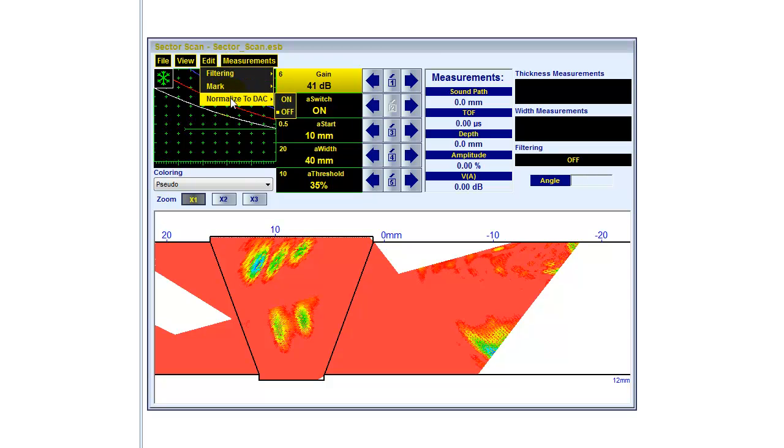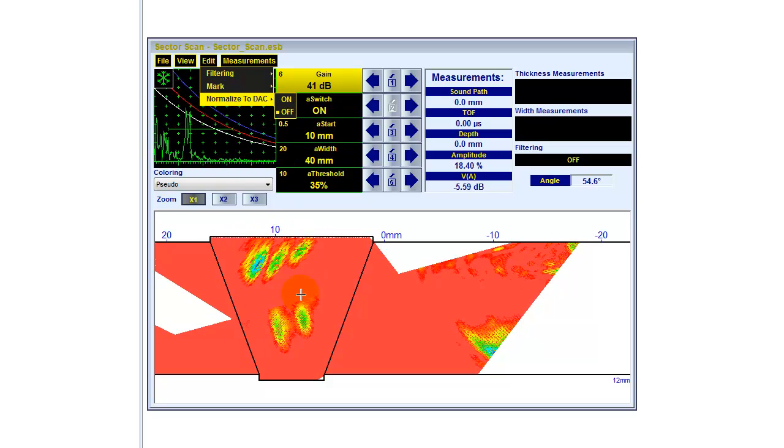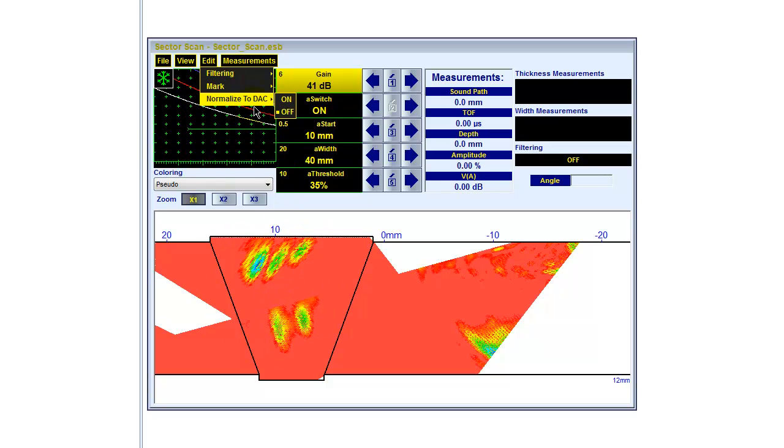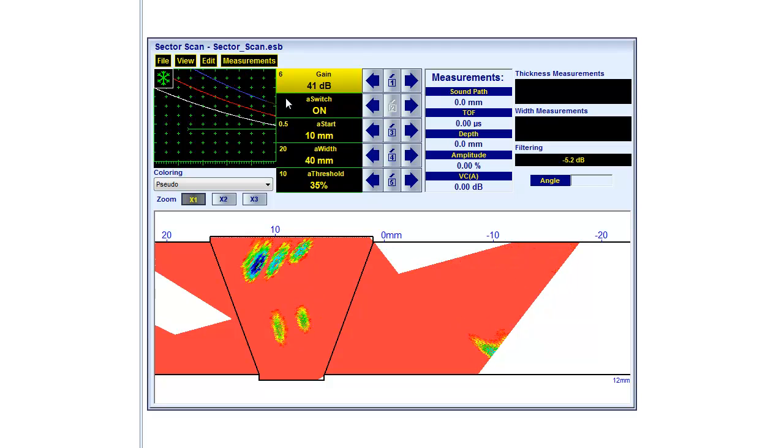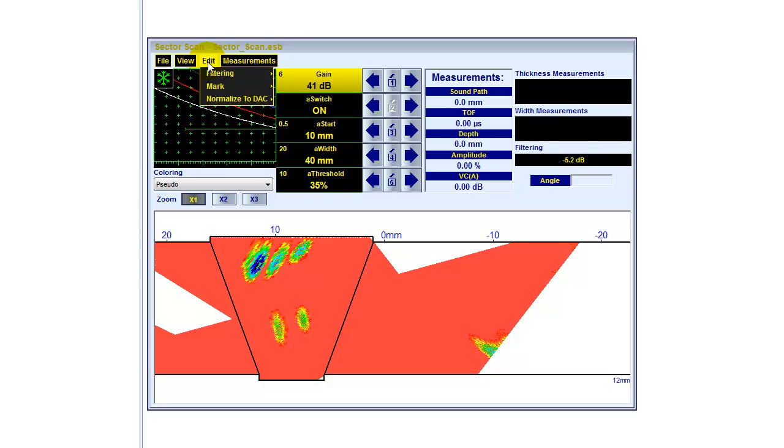I can normalize to DAC. Now we see DAC curves are shown on the A-scan. They are not activated yet. Only if I normalize the DAC, it's activated. And have a look at the indications here, the flaws. If I activate it, it is changing here. So now the DAC is active.